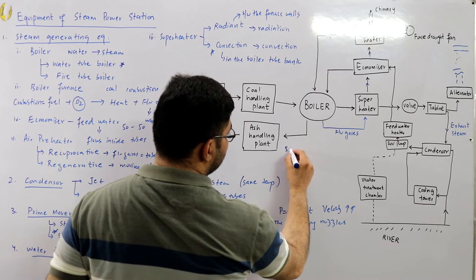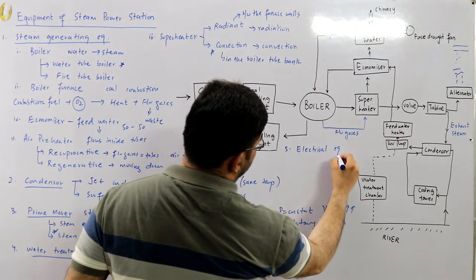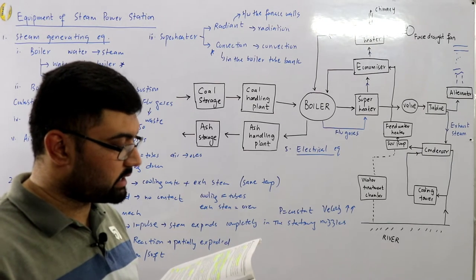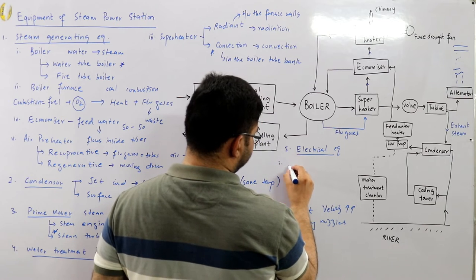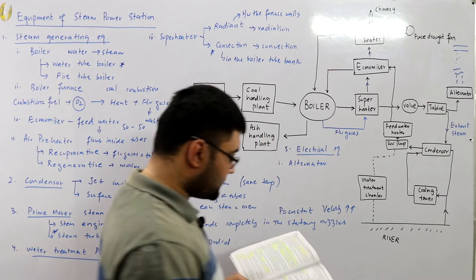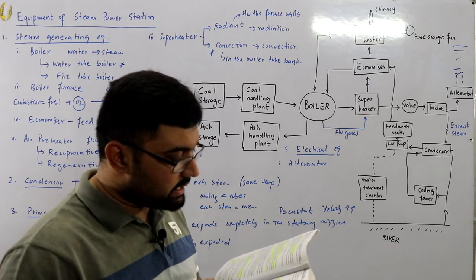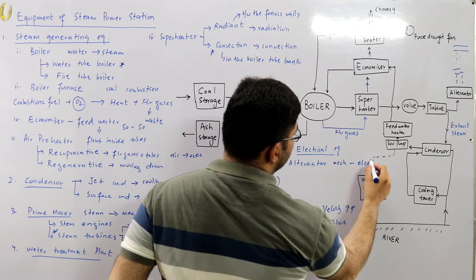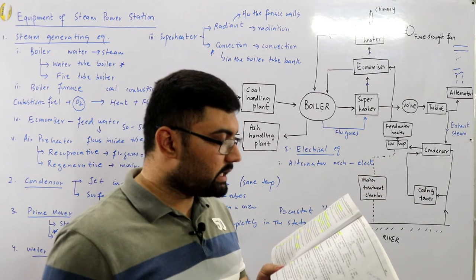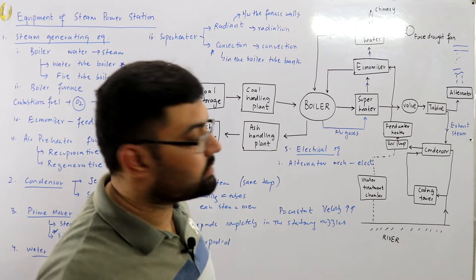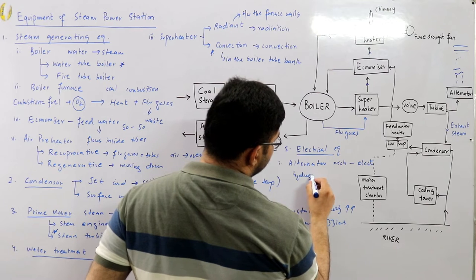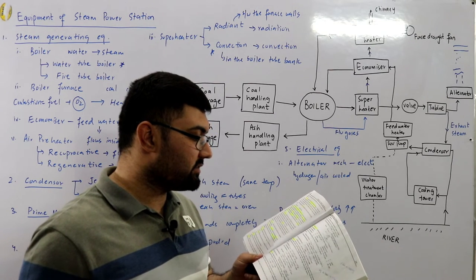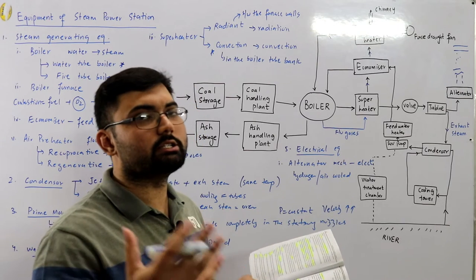Number five is the electrical equipment. A modern power station contains numerous electrical equipment; the most important ones are as follows. Number one is the alternator, which is coupled to the steam turbine and converts the mechanical energy of the turbine to electrical energy. The alternator may be hydrogen or air cooled. The necessary excitation is provided by means of main and pilot exciters directly coupled to the alternator shaft.